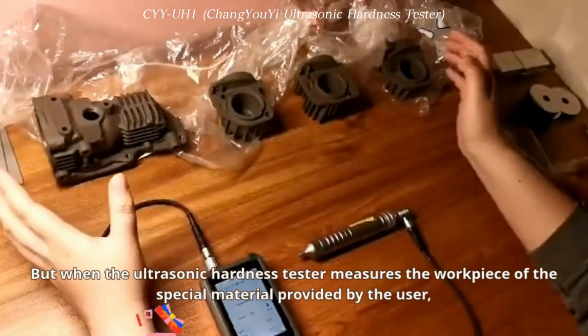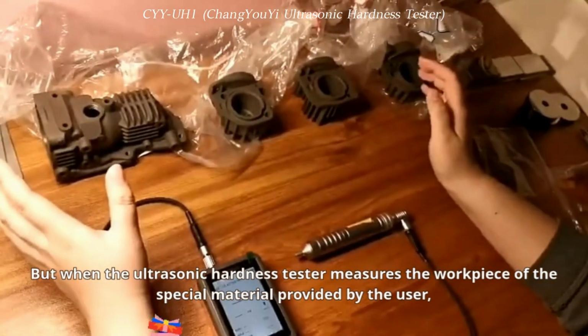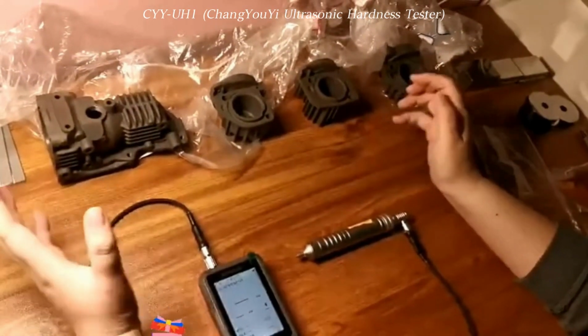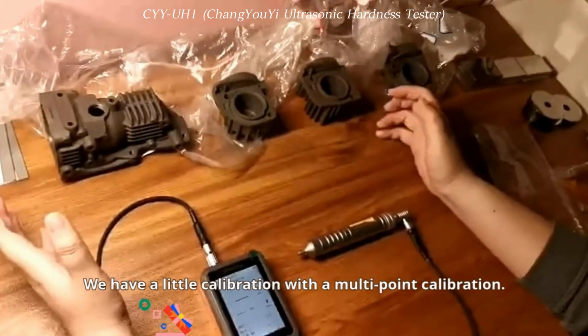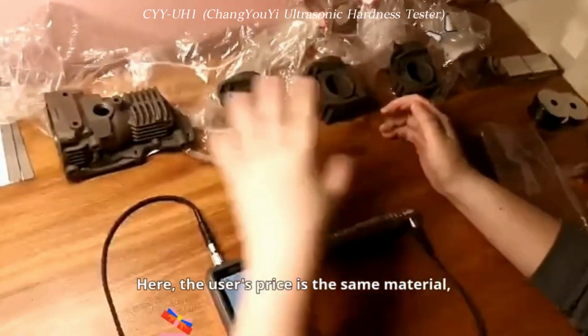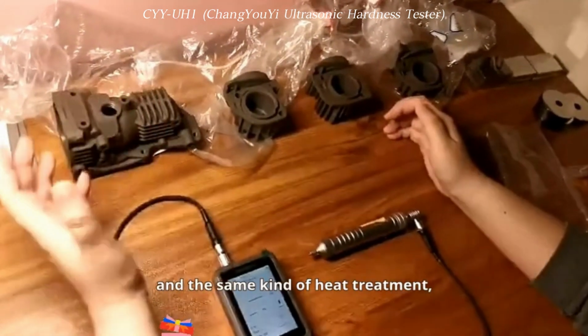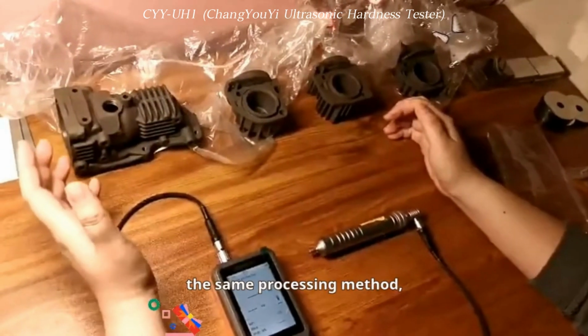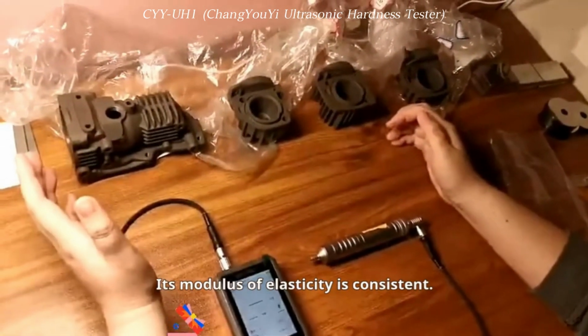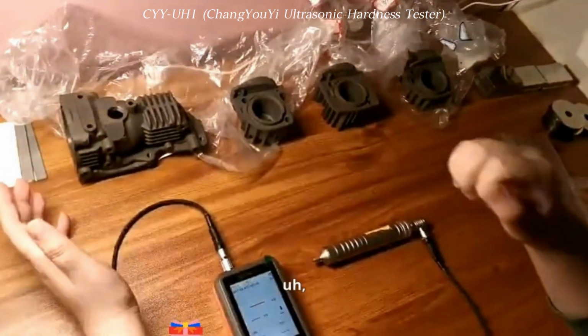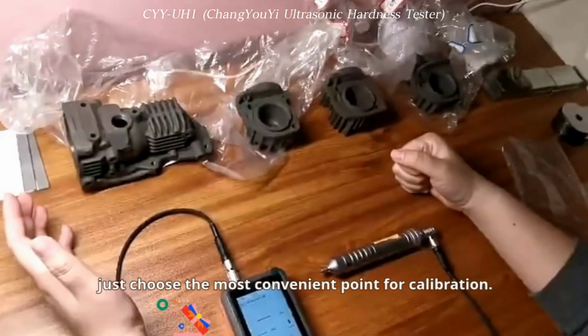But when the ultrasonic hardness tester measures a workpiece of a special material provided by the user, calibration is required. We use a single-point calibration. Here, the user's part has the same material, the same heat treatment, and the same processing method, so its modulus of elasticity is consistent. At this time, just choose the most convenient point for calibration.